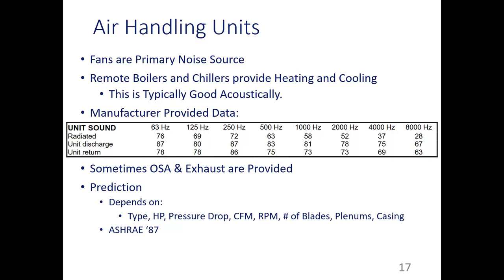So that happens when we have a source. But that should maybe be the difference between supply and return. There shouldn't really be much of a difference. The direction the air is traveling doesn't matter because the speed of sound is so much greater. But the fan might be offset to one end of the equipment, so as it goes through the unit, you have all the coils and other components, and there's going to be attenuation associated with that. Then you might have an elbow on the other end that's further away and bigger, and that might all be the return. So there are going to be plenums, silencers, elbows, some kind of lining inside the unit that's going to attenuate the return side more than the supply side before it comes out. That's why it's lower, and it helps a lot in making it work with what a common HVAC design is.